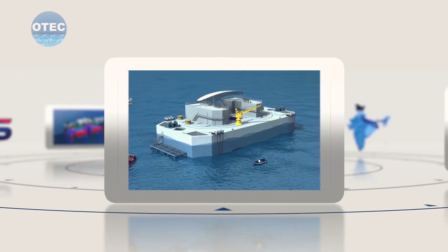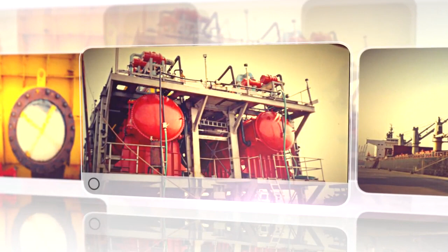India's first venture in OTEC started with designing a 1 megawatt OTEC plant by the National Institute of Ocean Technology under the Ministry of Earth Sciences. It was a floating plant where all the plant equipment was mounted on a 72-meter-long barge named Sagar Shakti. They included large plate heat exchangers for evaporating and cooling anhydrous ammonia, a 4-stage ammonia turbine, ammonia handling equipment and pumps for pumping voluminous quantities of surface and deep sea water.